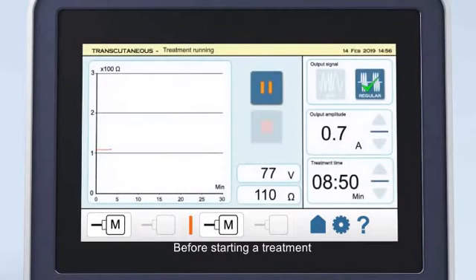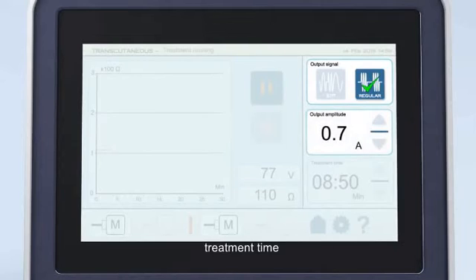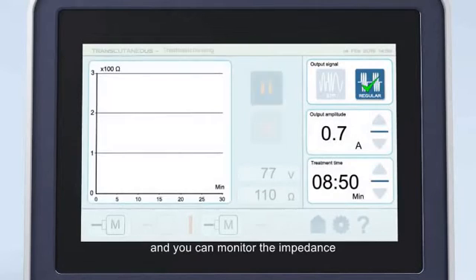Before starting a treatment you can set the output amplitude, treatment time and you can monitor the impedance.